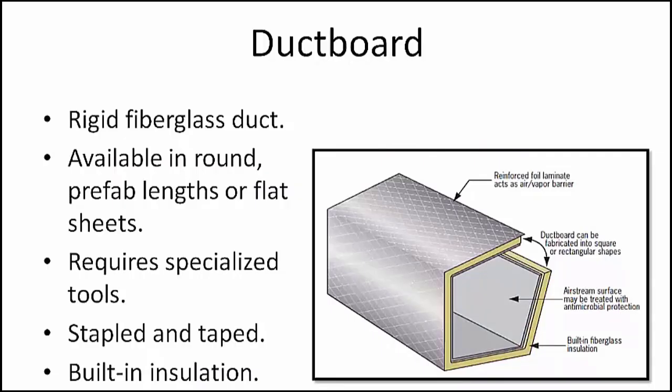Duct board is rigid fiberglass duct and is available either in round or prefabricated lengths or in flat sheets. Constructing and installing a duct board system requires specialized tools for creating the overlapping joints. When two pieces of duct board are joined, they are stapled with a special stapler and taped. The duct board in its design offers built-in insulation and is light and easy to transport.